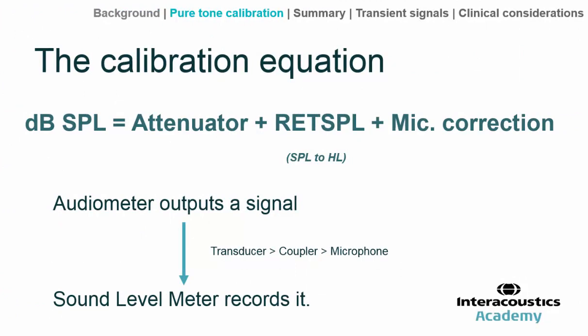To derive the target SPL, we refer to the calibration equation: target level in SPL equals the attenuator dial setting on the audiometer, plus the Reference Equivalent Threshold Sound Pressure Level, plus any correction factors required for that particular microphone and coupler. With this information we derive the target SPL, then use the sound level meter to check what it actually measures, confirming whether the target level and frequency match the reading.